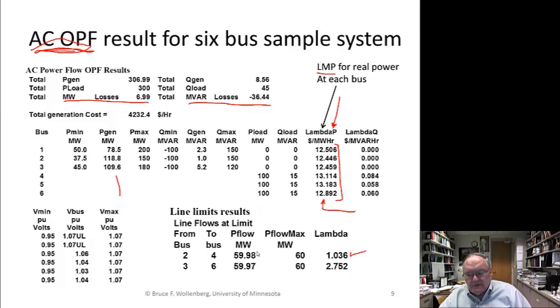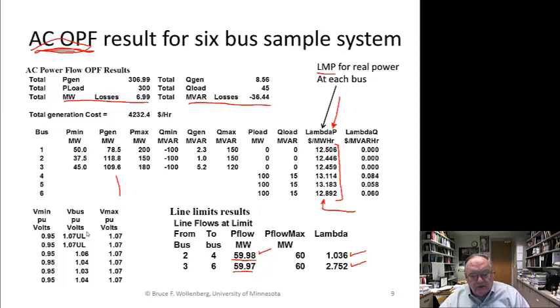We've limited the 2-to-4 line to 60 megawatts — it pulls to 59.98 — and 3-to-6 to 59.97. There's a Lagrange multiplier associated with each of these. For voltages: the first two buses are generator buses and both go to the maximum voltage — they push up to the maximum, which gives some more minimization. The other three are still just below the max, but the voltages go up too.